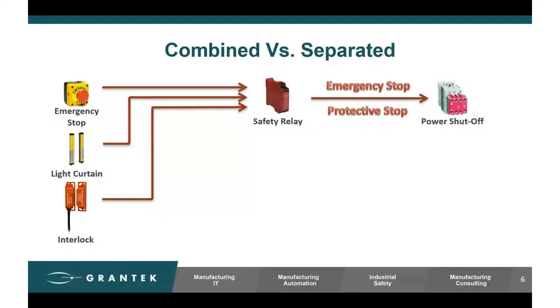In this case, we'll assume a couple of interlocks and a light curtain. What do most engineers do? Well, they run those safeguarding devices right into the same relay, executing the same emergency stop function. So if you hit the e-stop or trip any safety device, the same end result occurs: power is removed everywhere. Once again, is this wrong? No, it's just probably not optimized.